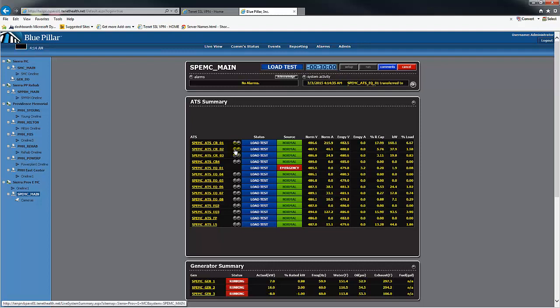And while I do this, keep in mind that since you guys are having problems with ATS CR01, if it's not the initiating ATS, you guys want to leave that one to the end. And as you can see in this video, that's exactly what I'm doing. I'm leaving ATS CR01 until the very end, and then I'm waiting for all the ATSs to transfer over. And I'm doing this because of that data loss error that you guys are obtaining right now because of the problems with your IT equipment.